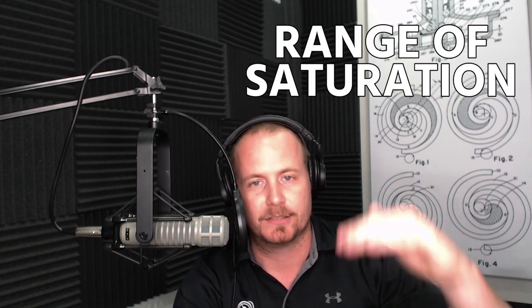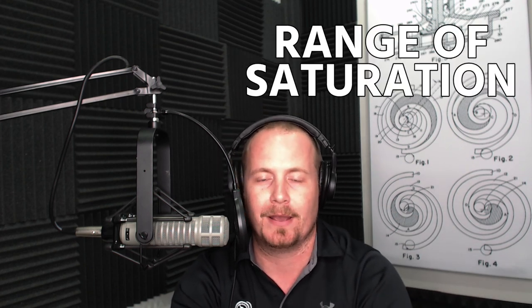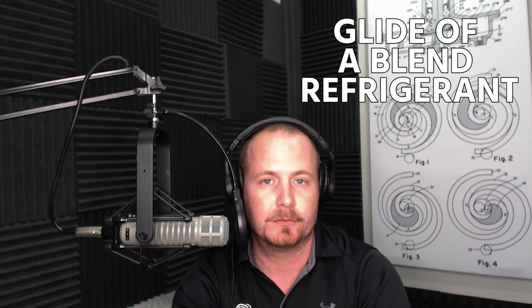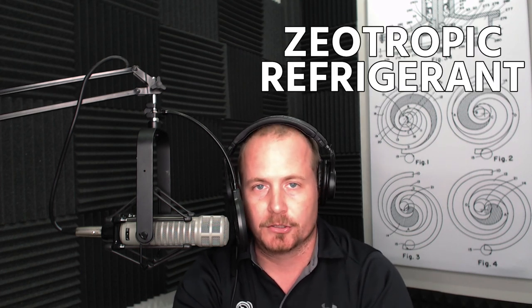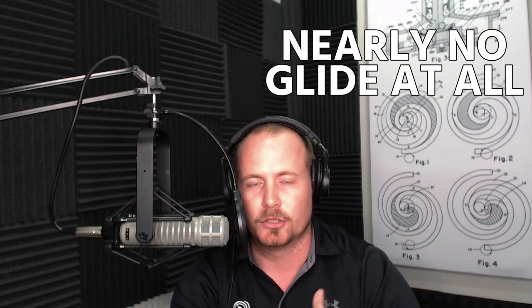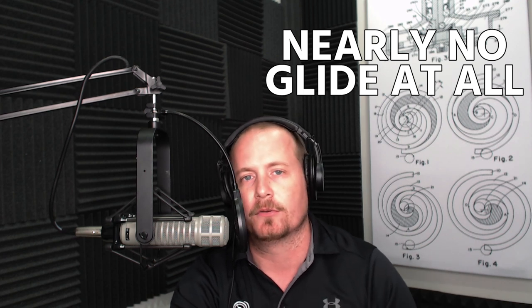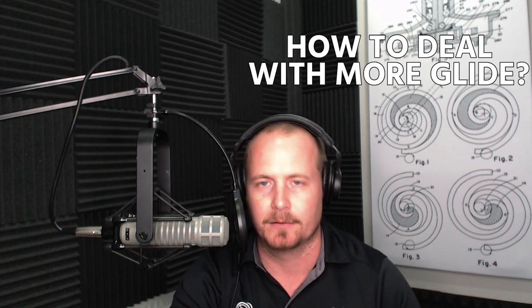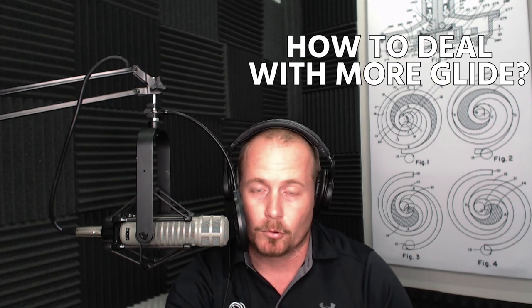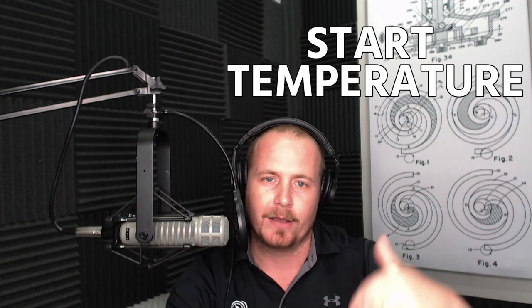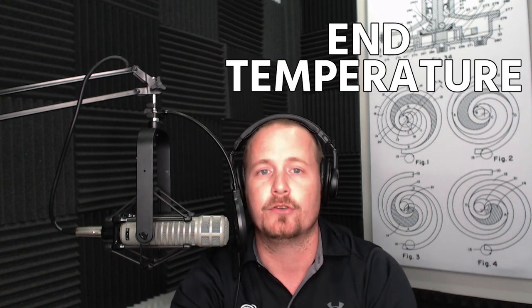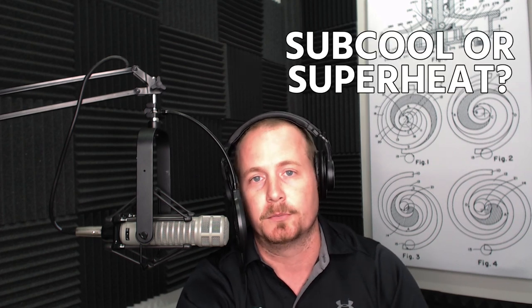That's that range of saturation when you have glide on a blend refrigerant, which is what we call a zeotropic refrigerant. 410A, with only that tiny amount, we call a near-azeotrope. So that means it has nearly no glide at all. We're used to working in air conditioning with R22 and then with 410A, so we haven't used a lot of glide. Now when you go into a lot of these blends or a lot of the modern refrigerants, you're starting to find more glide. So you have to learn how to deal with that. You have the temperature that it starts boiling at, and then you have the temperature that it ends boiling at. But here's how you can remember which is used for subcool and which is used for superheat.